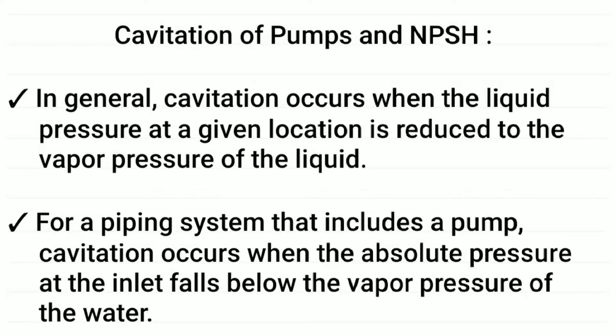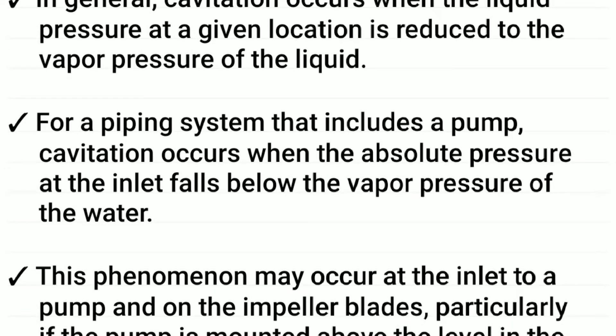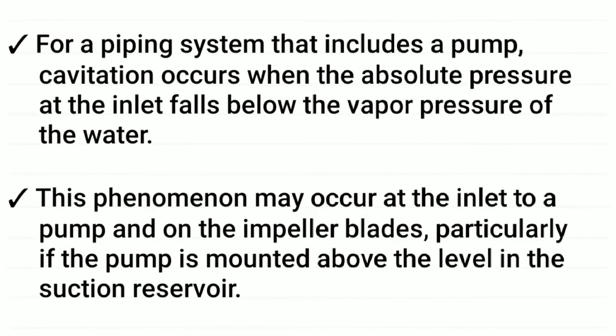Cavitation of pumps and NPSH. In general, cavitation occurs when the liquid pressure at a given location is reduced to the vapor pressure of the liquid. For a piping system that includes a pump, cavitation occurs when the absolute pressure at the inlet falls below the vapor pressure of the water.